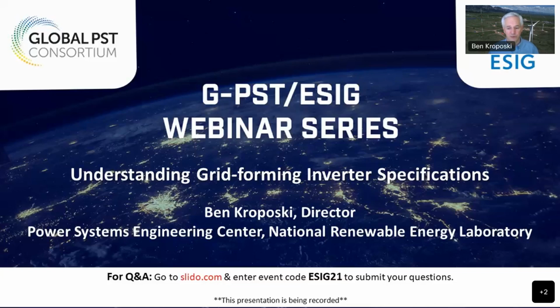We do have one of our working groups inside UNIFI that is working on control algorithms, and probably that particular topic of where do you start to set your gains on the variety of control algorithms and parameters that are being used is a whole other webinar or topic. But what we're trying to do is come up with some general specifications so that moving forward, people have a good idea of what are appropriate values for some of the basic settings inside these different control algorithms. Even inside grid forming, there's at least 3, if not more, 5 plus types of grid forming algorithms that are out there and published. They all have different types of settings that are important to understand how they work in order to maintain stable operations.